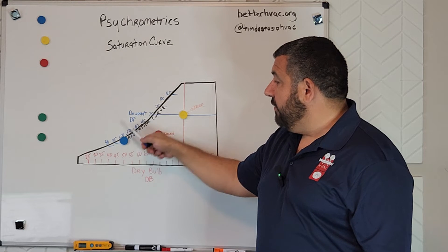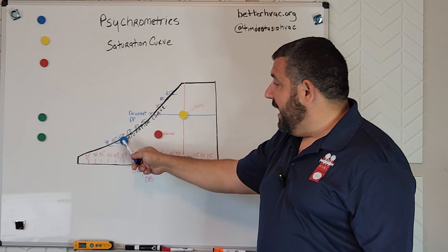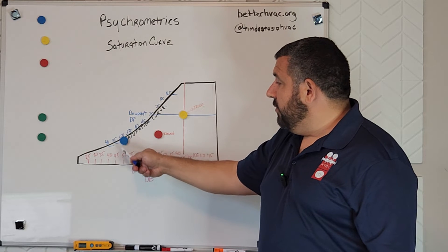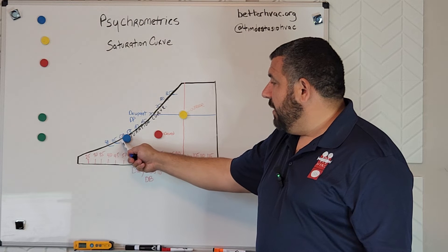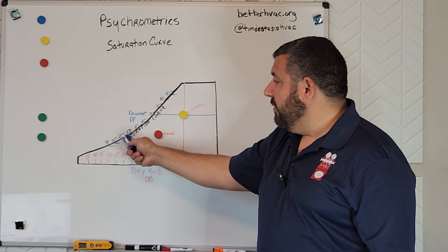We get to our saturation curve and we slide down the slide until we cool it down to a point of somewhere around 55 degrees and around 50 to 55 degree dew point.